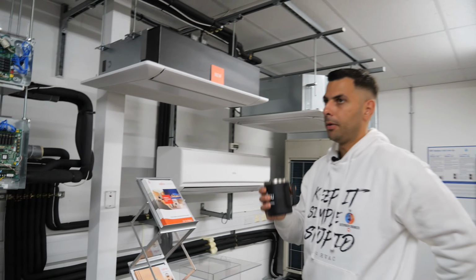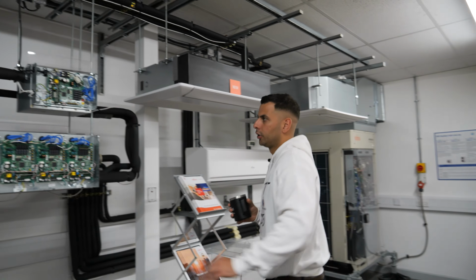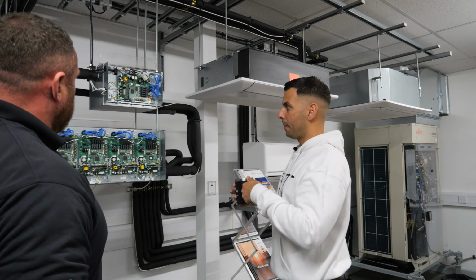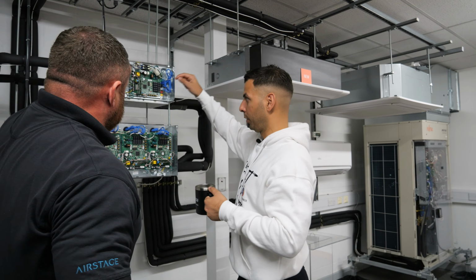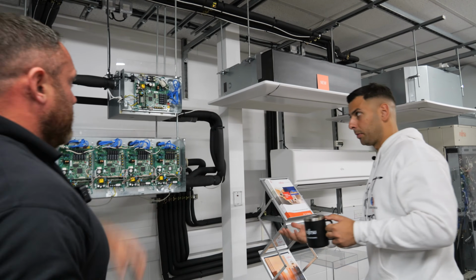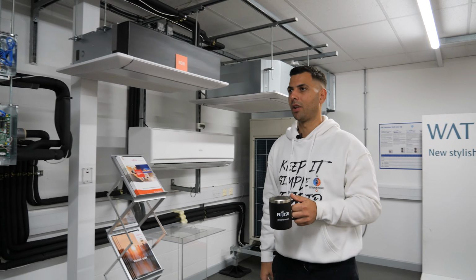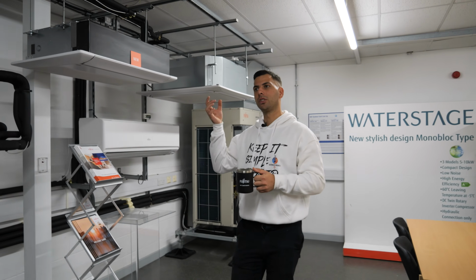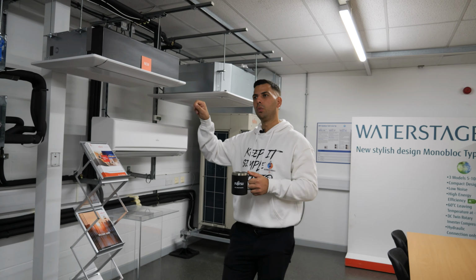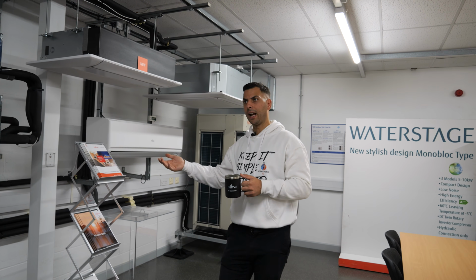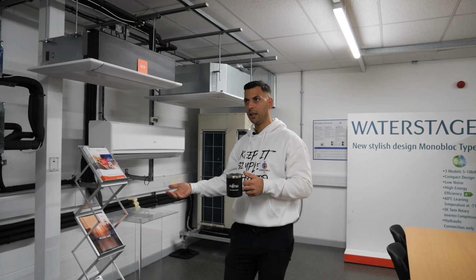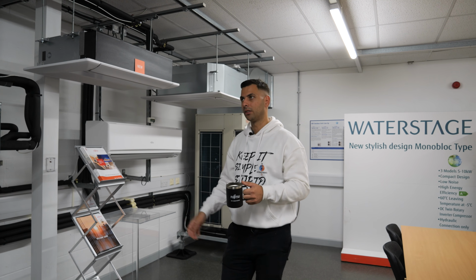So with a single BC box, how does that work? You chain them in, run a cable, and it's just two indoor units, two cores, and there it goes. Some of your competitors, unfortunately, have separate relay boxes with a ribbon cable, which is an extra half an hour. When you've got 100 fan coils, that could take you 2 or 3 weeks just putting in the relay boxes.